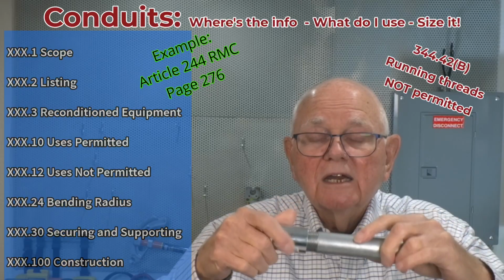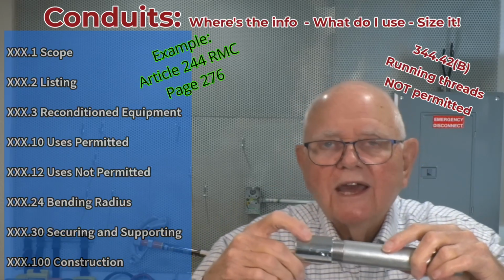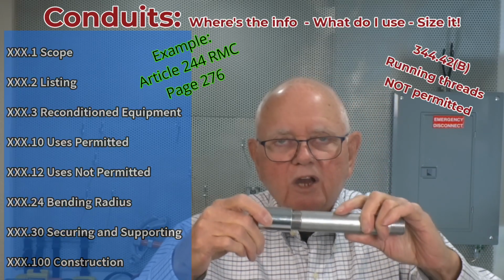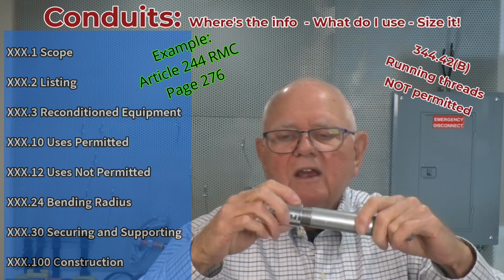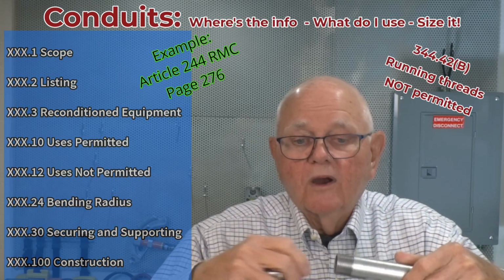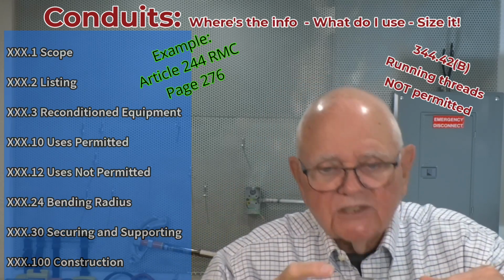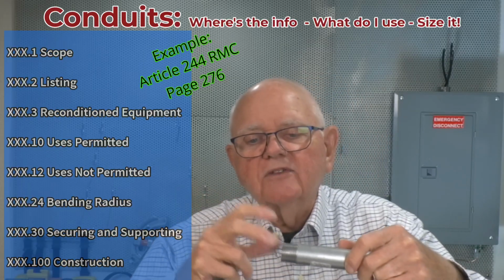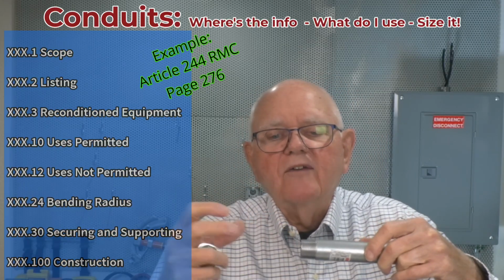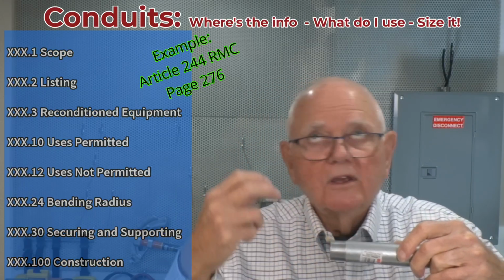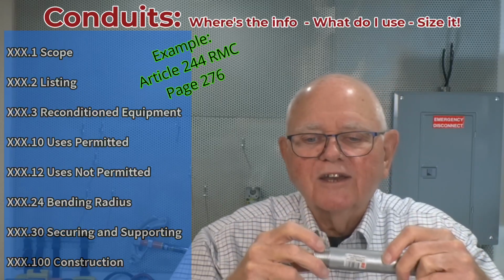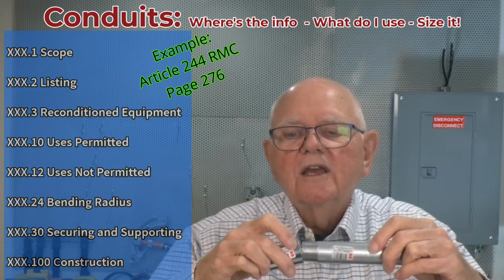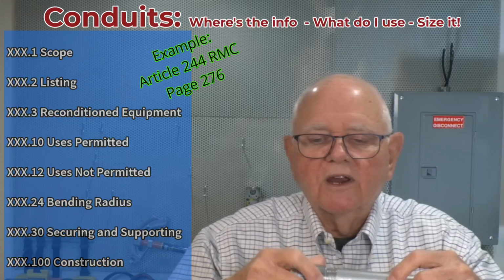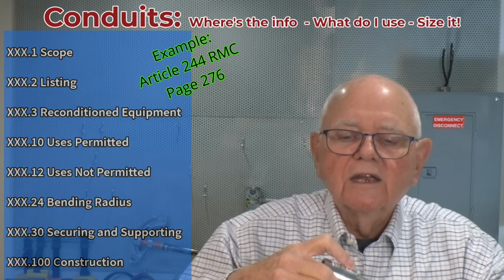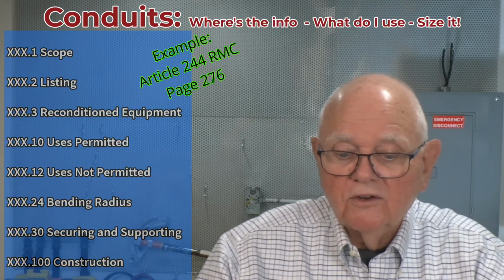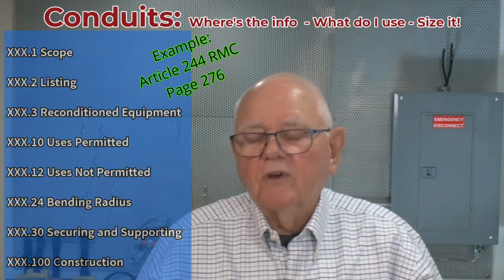There's some good NECA standards on how to thread conduit. Of course, the code doesn't give you the specifics on how to use sharp dies and how to use your dies depending on the type of threader that you're using, and how far back to cut the threads, and use lots and lots of oil for cutting the threads and so on and so forth. Those specifics you're going to find elsewhere, not in the code book. But anyway, you need to learn. If you're going to thread conduit, make sure that you learn how to do that properly if you're not already doing that, okay?